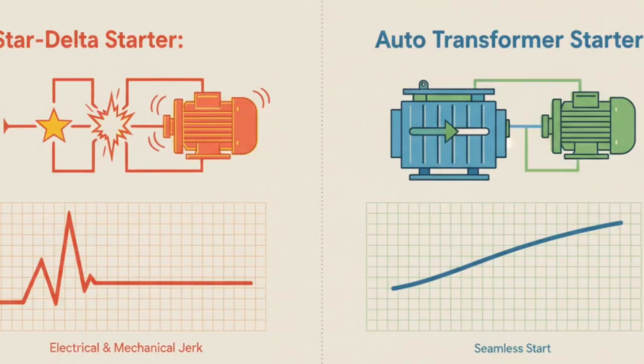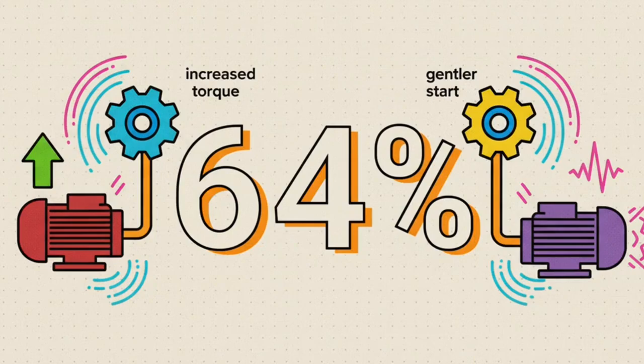Now, the classic, cheap and cheerful solution was the star-delta starter. It works, sure, but to get to full power, it has to briefly disconnect and then reconnect the motor. And that switchover causes this huge electrical and mechanical jolt. A much smarter, smoother solution is the auto transformer starter. It uses a transformer to ramp up the power in steps, completely eliminating that harsh jerk and giving the equipment a much gentler start. And this number right here, this just says it all.